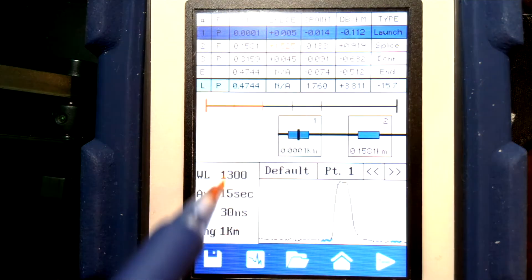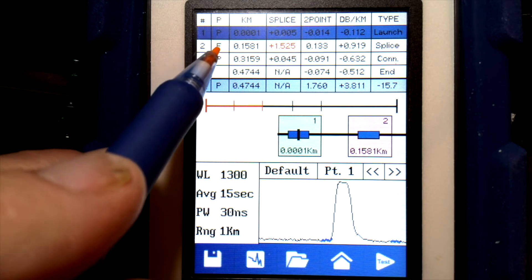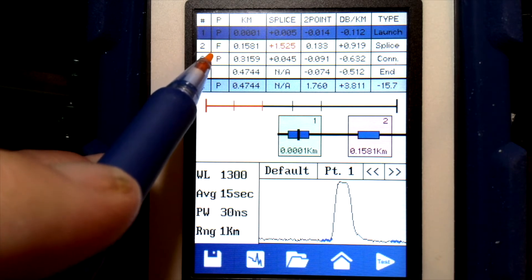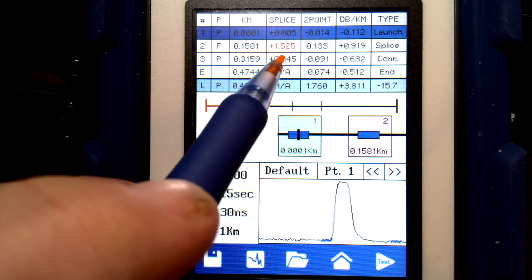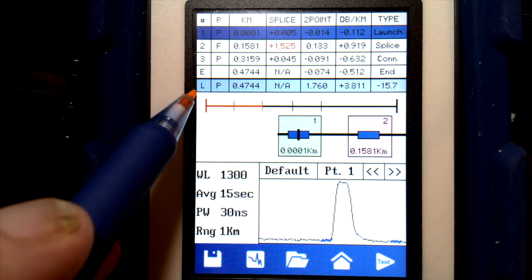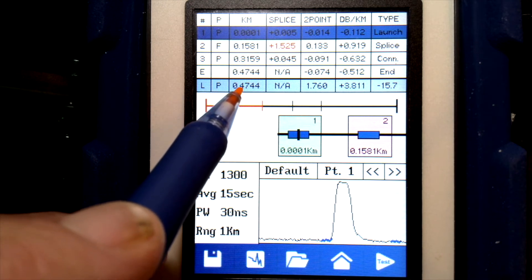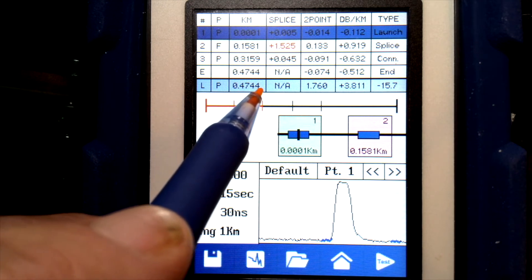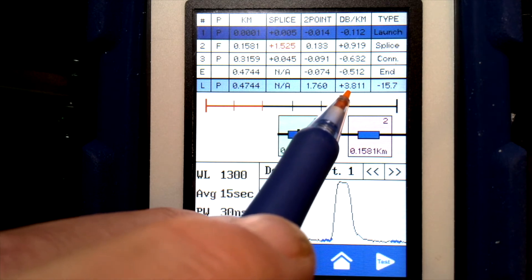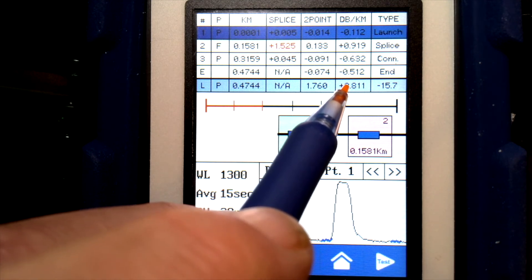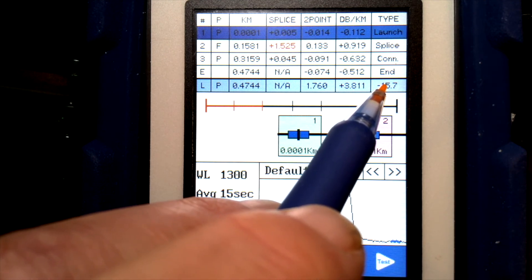If we go to the next screen, we have the event table. This shows us the events with a pass/fail indication for each one — the type of event, where it is, and the loss. The gray line at the bottom is the total link, telling us the total loss of the whole link, which in this case is 3.8 dB including all the connectors and fiber.